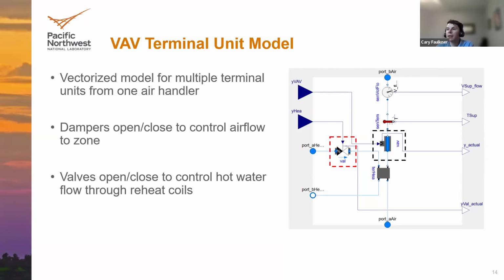And then we have the heating, the reheat coil valve. A lot of times VAV systems might have electric reheat coils, but in this model, it's a hot water heating coil, which includes a valve to modulate the water flow through the reheat coils to meet the reheat demand. So you can see a different blue loop there representing the hot water loop and connecting to the hot water sources to model that flow of water through that. And then you have the bidirectional flow of water through the heating coil within the terminal unit itself.